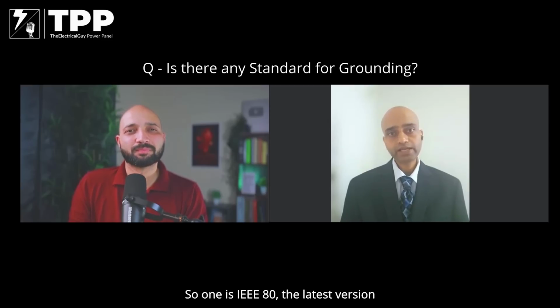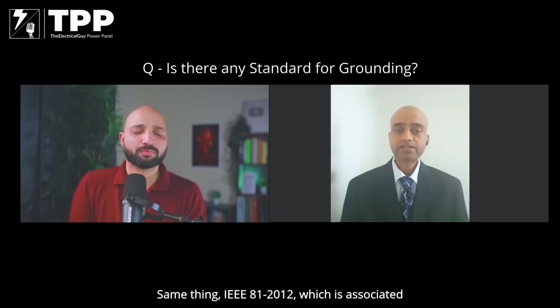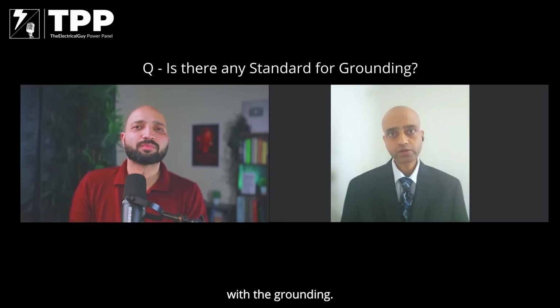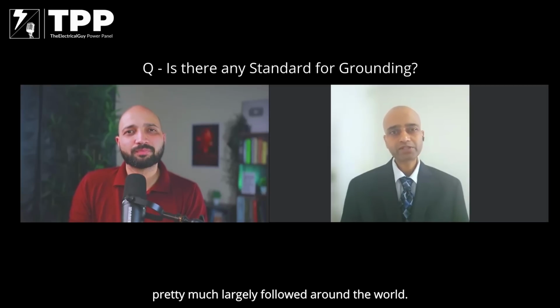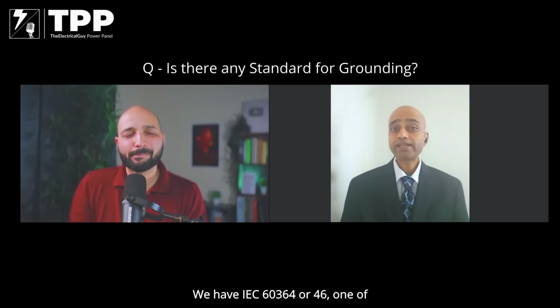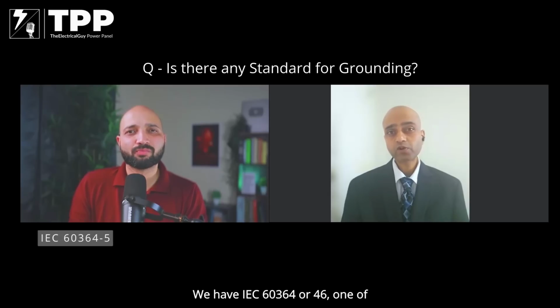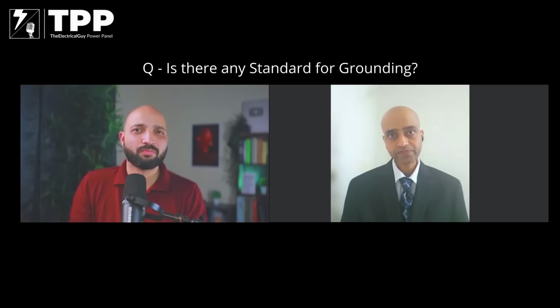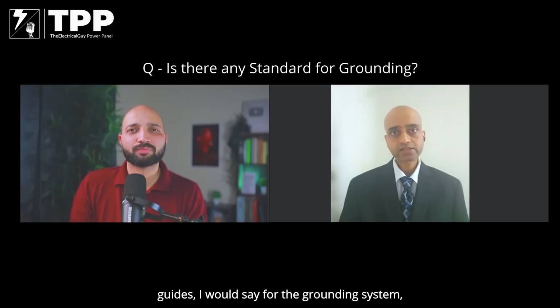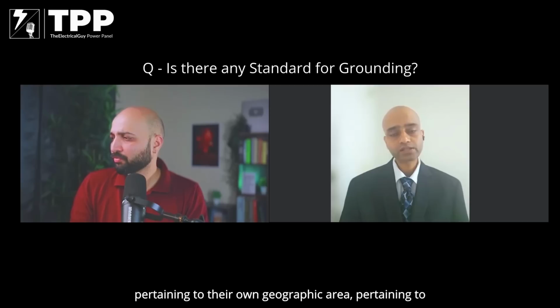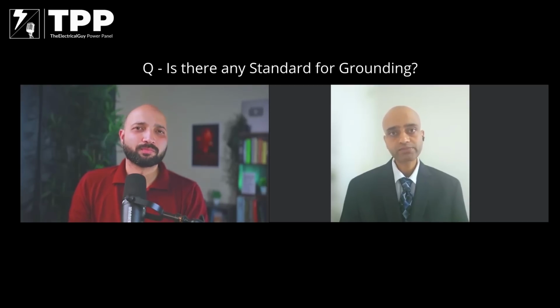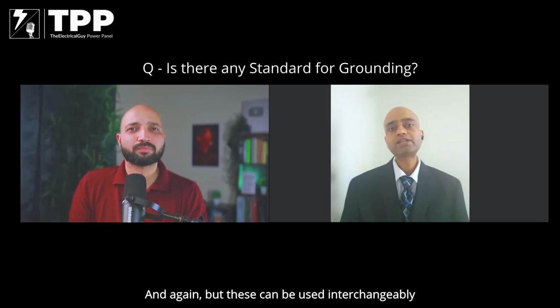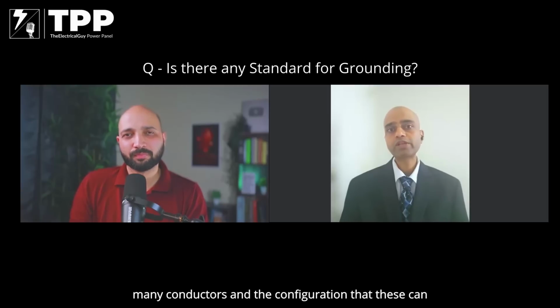One is IEEE 80. The latest version is IEEE 80-2013. Same thing, IEEE 81-2012, which is associated with grounding. That's for North America, but pretty much largely followed around the world. We have IEC 60364 or similar for Europe. We have the Indian standard IS 3043 for grounding. Apart from that, these are the guides, I would say, for the grounding system pertaining to their own geographic area and their own systems. But these can be used interchangeably because there are only so many conductors and configurations that can be used interchangeably.